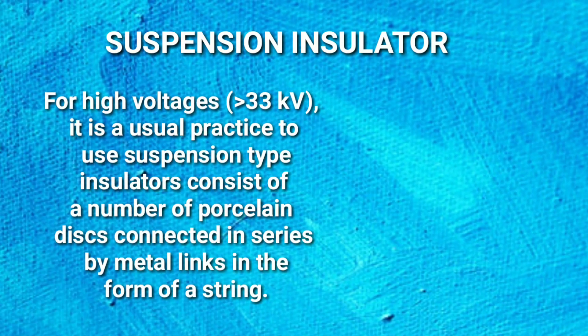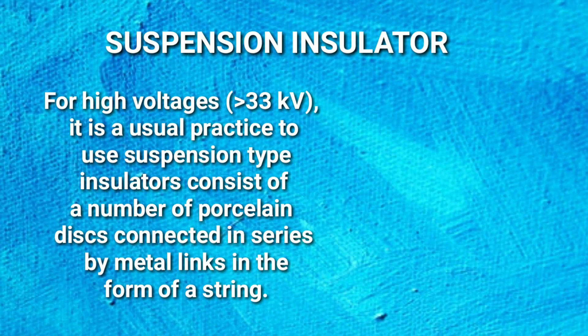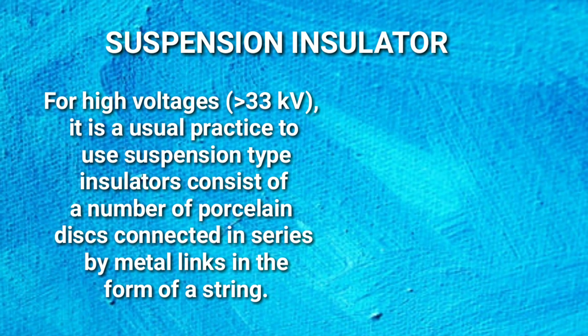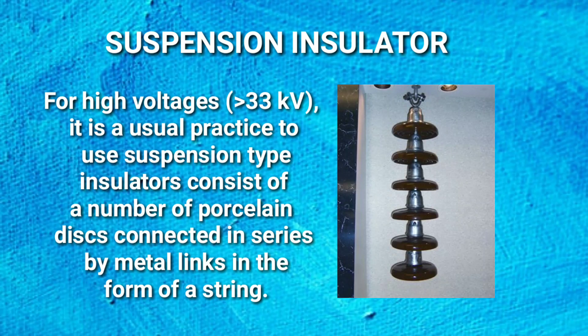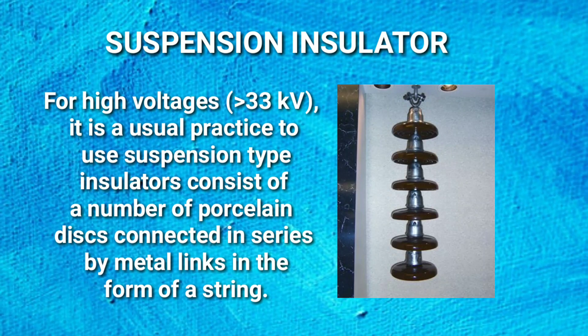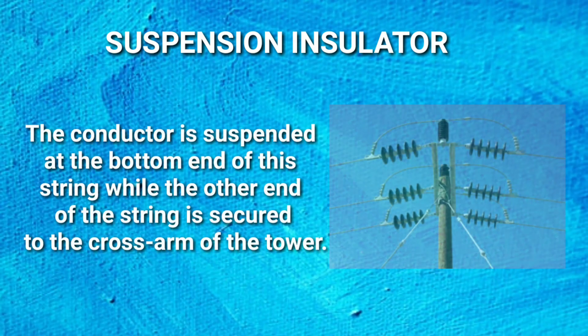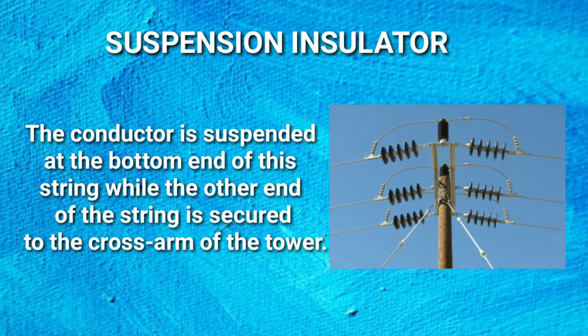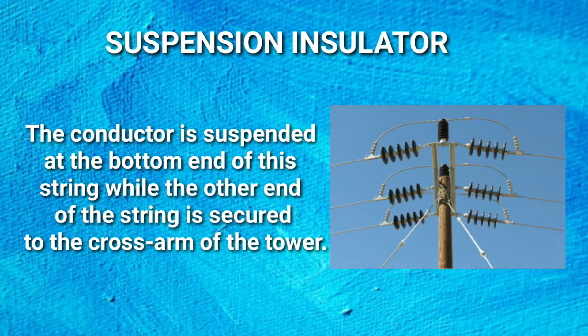Suspension insulator: for high voltages greater than 33 kilovolts, it is a usual practice to use suspension insulators, which consist of a number of porcelain discs connected in series by metal links in the form of a string. The conductor is suspended at the bottom end of this string while the other end of the string is secured to the cross arm of the tower.